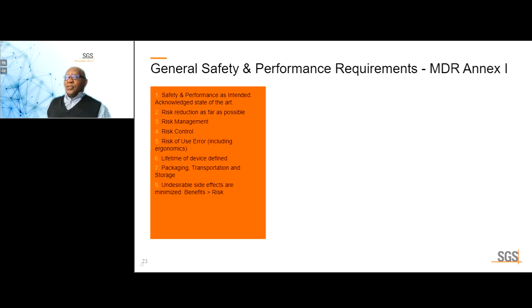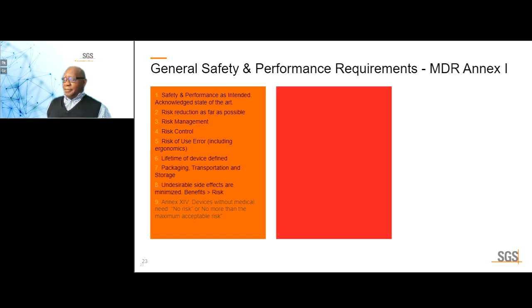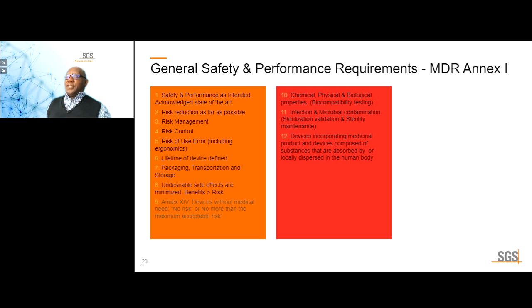GSPR 4 talks to risk control. 5 talks to risk of use error, including ergonomics. GSPR 6, lifetime of the device defined. GSPR 7, packaging, transportation, and storage. And GSPR 8, undesirable side effects to be minimized, whereby the benefits must outweigh the risks. GSPR 9 really doesn't apply to mainstream medical devices because it talks to devices without a medical purpose. Then the other GSPRs are 10, 11, 12, 13, 14, 15, 16.